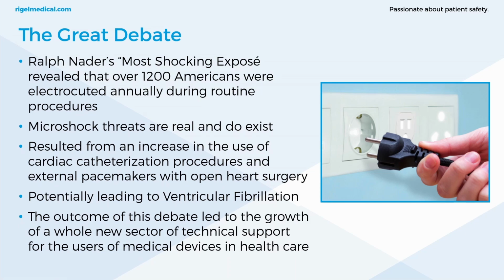And it all comes back to Ralph Nader's most shocking exposé that revealed that over 1,200 Americans were electrocuted annually during routine procedures. Now, with this being back in 1971, most of you are probably already aware of this exposé. It comes up time and time again. The risk is obviously greatly reduced in the modern world because medical devices have thankfully greatly improved in their safety, but the risk is still there. The microshock threats are real and they do exist.